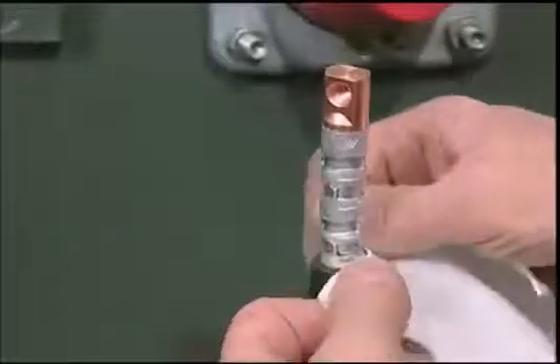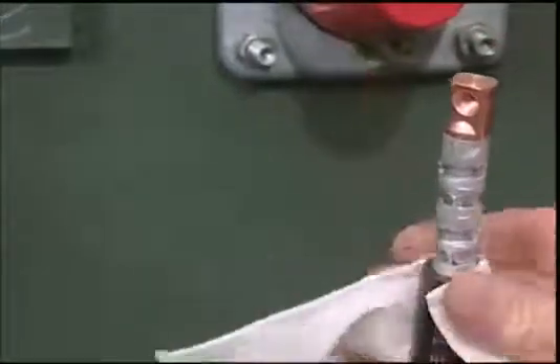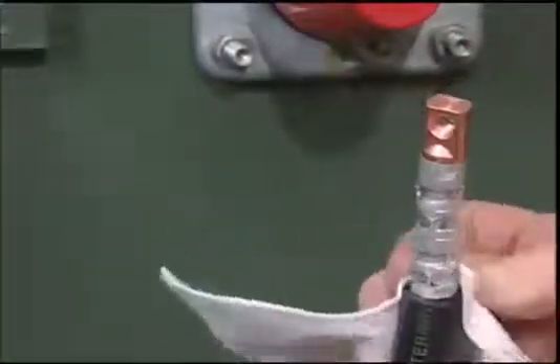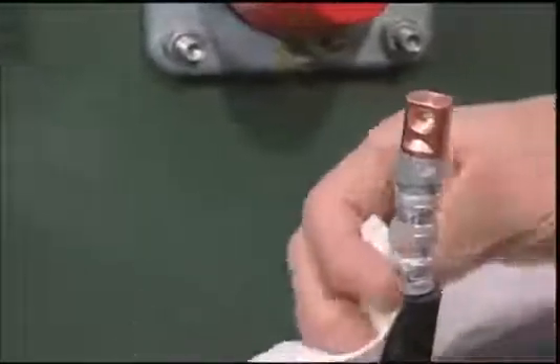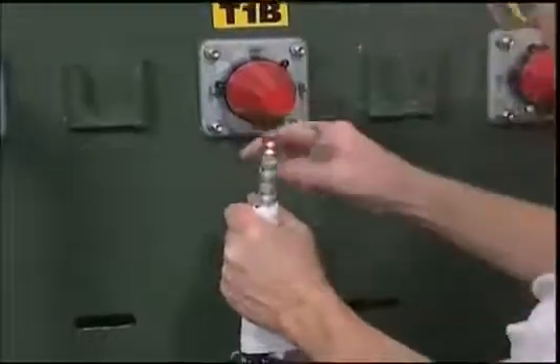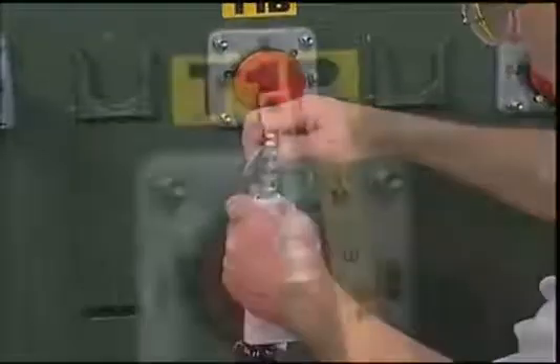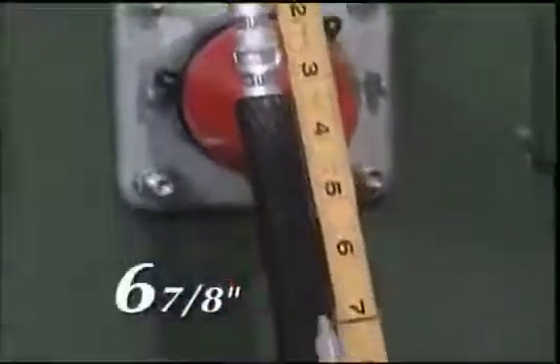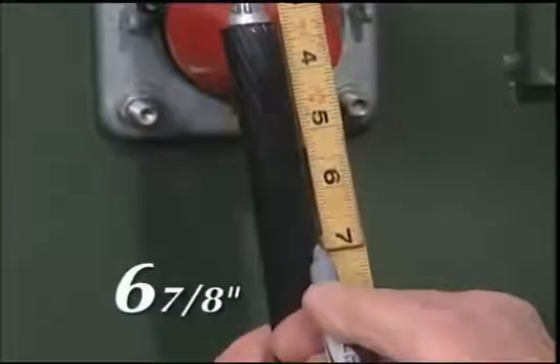After crimping, remove any excess antioxidant with a lint-free cloth. It's important that the antioxidant not contaminate the cable. Make sure you remove any sharp edges on the connector after crimping. Now, measure 6 7/8 inches from the top of the crimp connector.